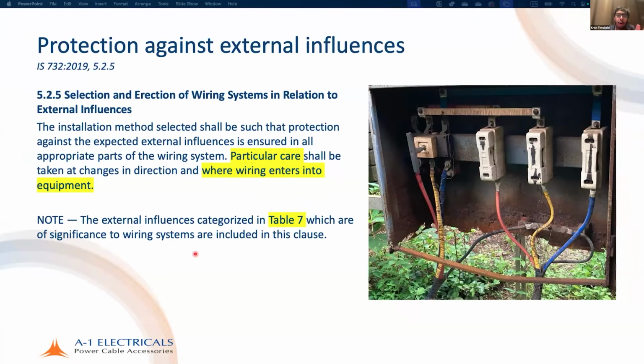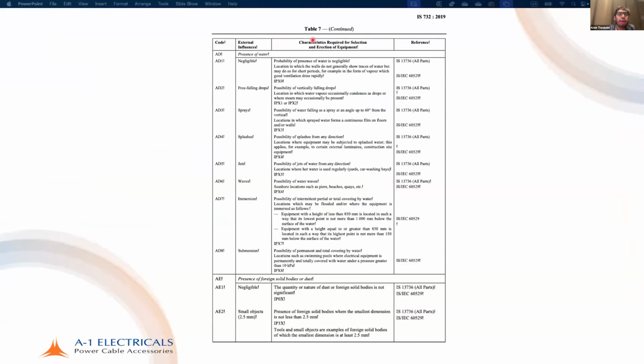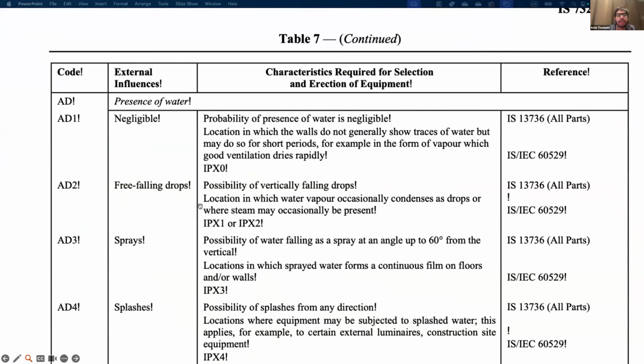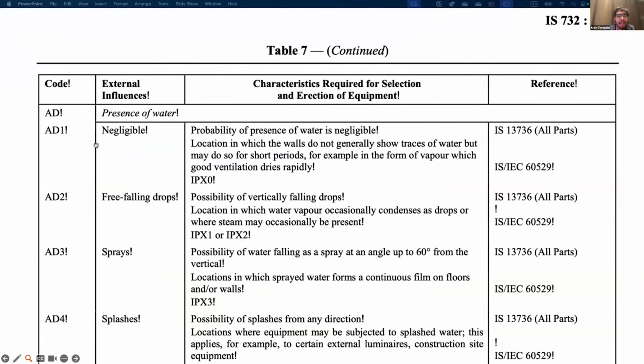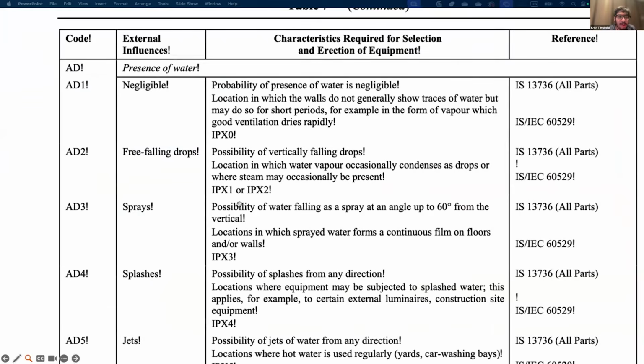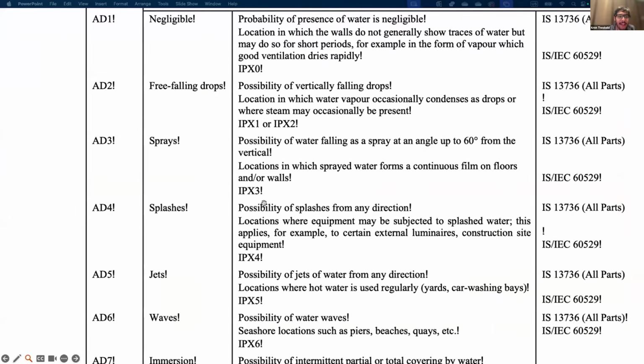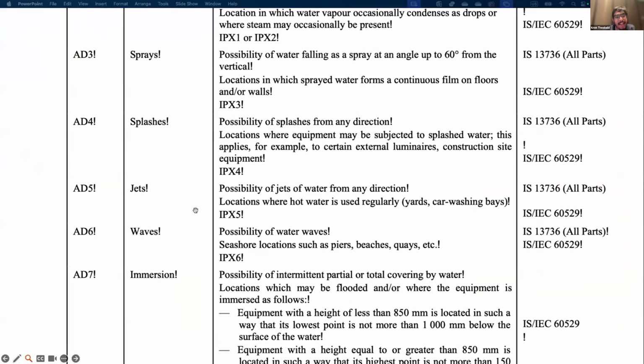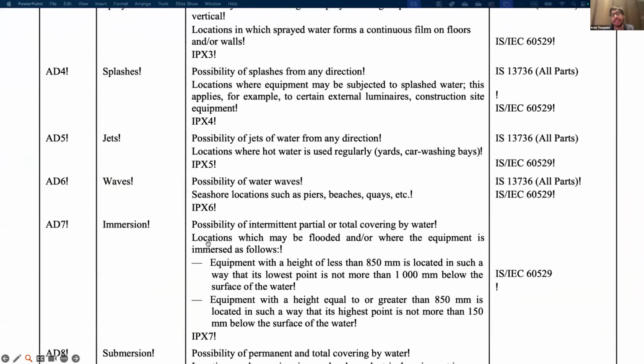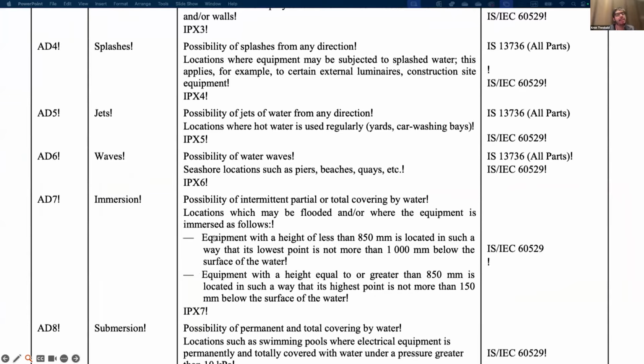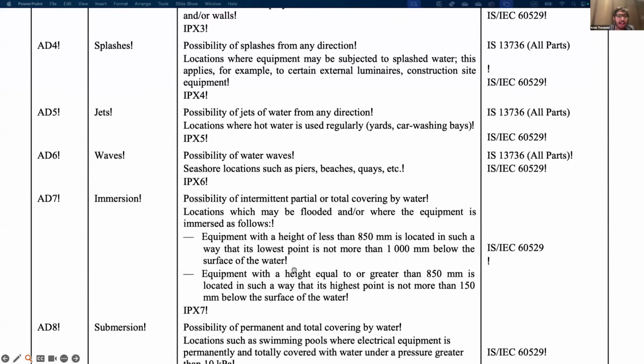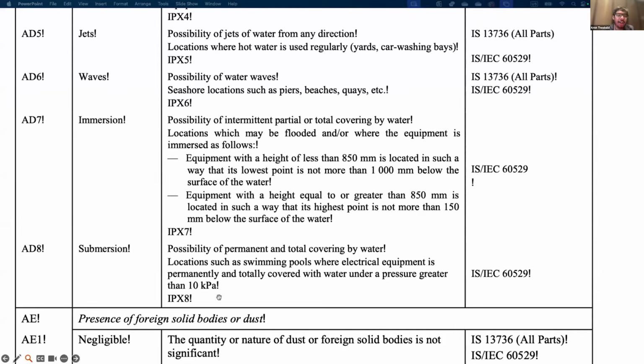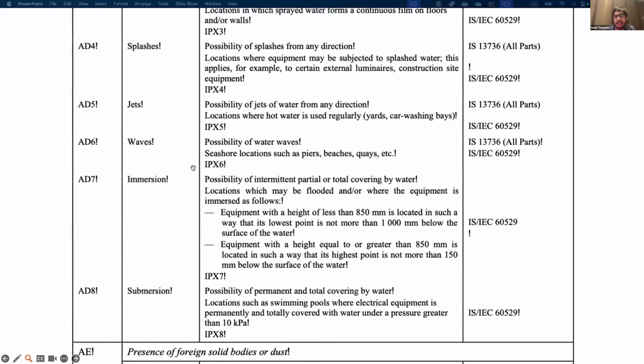Yeah, and now when we talk about external influences, they are categorized in Table 7 of IS 732. So you go to Table 7 here, for example, presence of water. Negligible presence of water means AD1, so IPX0. Free falling water means IPX1 or IPX2. If there are sprays, then IPX3. If there are splashes, then IPX4. If there are jets, then IPX5. If there are waves, then IPX6. If there is immersion, for example, something that may be flooded for some amount of time, then that is the case. If it is entirely designed to be submerged and the pressure is greater than 10 kilopascals, then it's IPX8. So very important, you need to understand what the relevant external influences are.